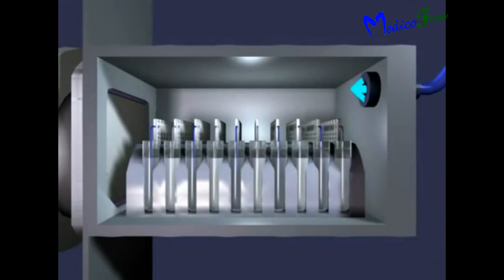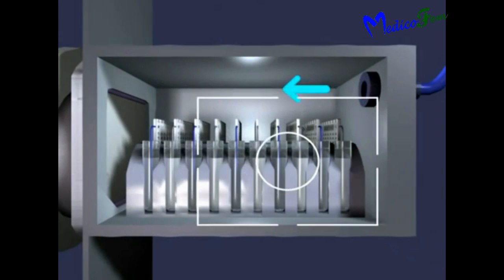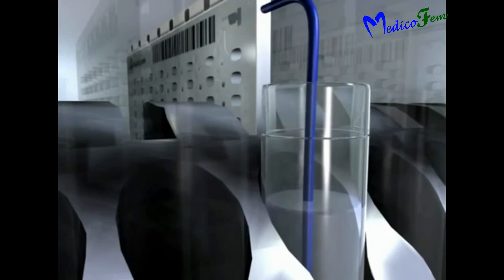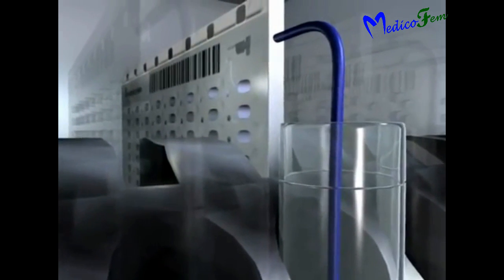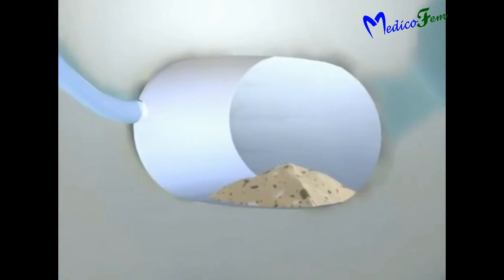Now with positive pressure, that pushes suspension inside the card and fills all the chambers present in that card. Dehydrated reagent or drug are dissolved in this suspension.